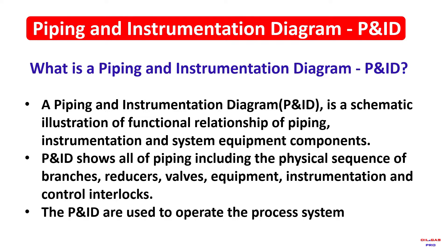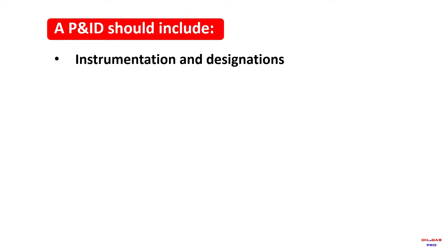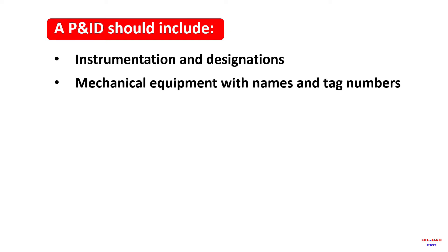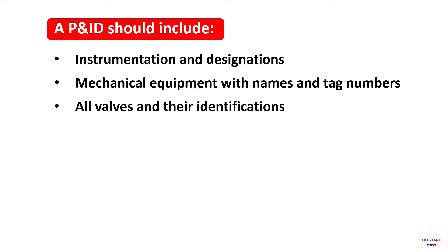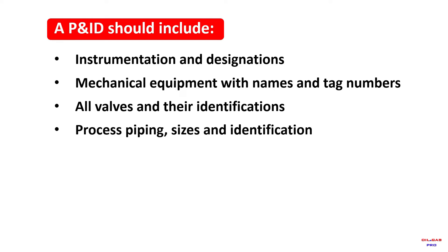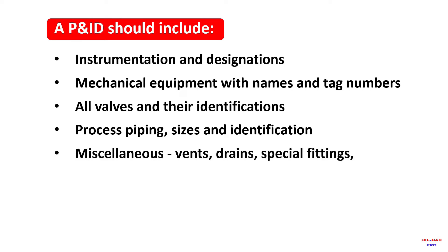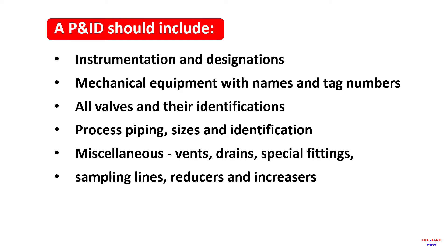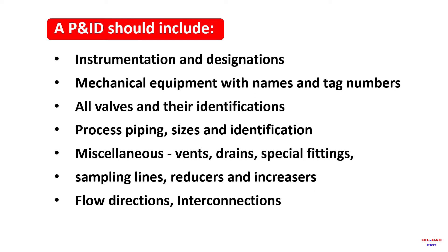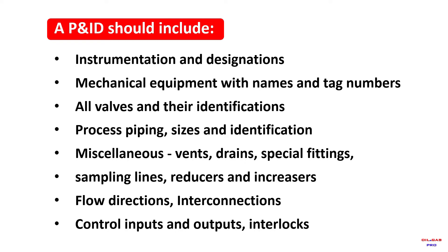The P&ID is used to operate the process system. The P&ID should include instrumentation and designation, mechanical equipment names and tag numbers, all valves and their identifications, process piping sizes and identification, miscellaneous vents, drains, special fittings, sampling lines, reducers, flow directions, interconnections, and control inputs and outputs interlocks.